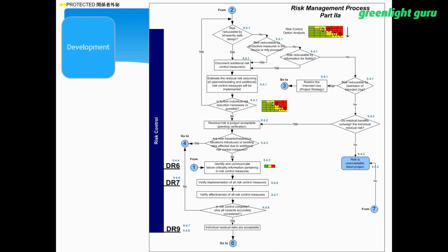And if I can pass all those tests according to the criteria that I have set for success, and it makes sense logically and statistically, I've not seen a situation where an FDA investigator will look at me and say, I don't think that's as low as practical. I haven't had that experience. However, I've been blessed with design engineers, advanced quality engineers, and people in statistics that run circles around me in technical issues, who have always, in my instance, been able to make that case.